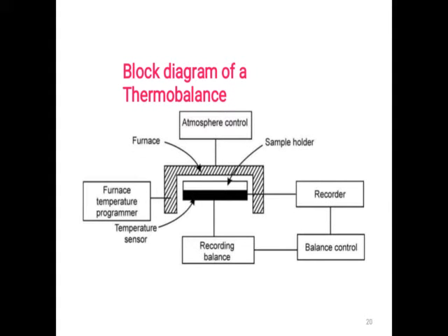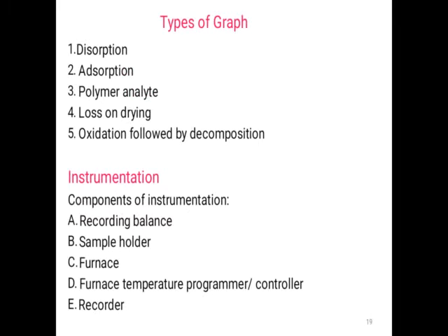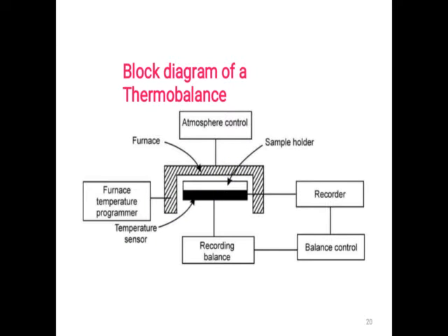Okay, so this is a block diagram for the thermobalance. What we require in the instrumentation is, first, a recording balance. Here you can observe that a recording balance is present. It is useful for recording the weight of the sample at every moment during the process.